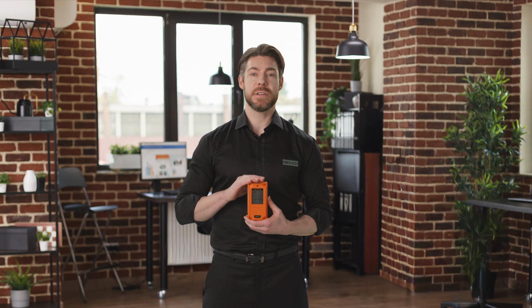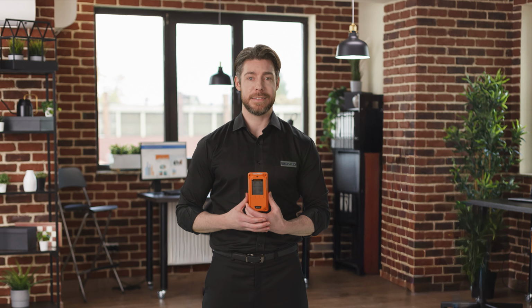The SP-MGTP features an LCD with backlight and indicator LEDs, providing clear visibility in a wide range of working environments. The device is operated using 3 control buttons, allowing simple operation and easy configuration. At the core of the SP-MGTP is a powerful gas detection system. It supports a wide range of sensing technologies, including electrochemical sensors, PID sensors, catalytic or NDIR sensors. It is actively sampled by a built-in pump with a flow rate of 250 to 300 cc per minute, ensuring fast and accurate gas measurement. For enhanced safety, the SP-MGTP provides multiple alarm methods, including visual alerts on the LCD and indicator LEDs, as well as a loud audible alarm of 90 decibels at 10 centimeters.